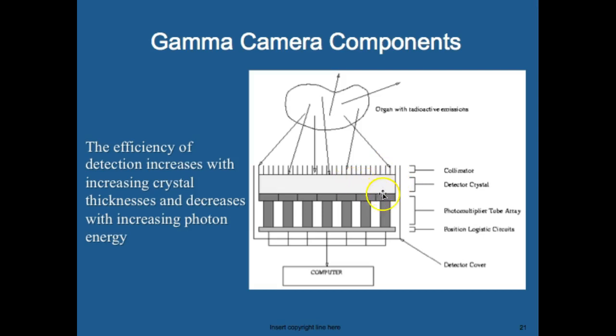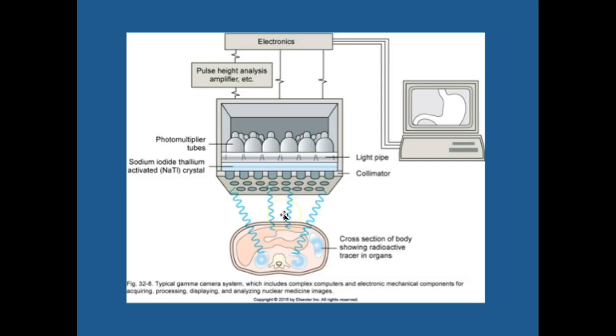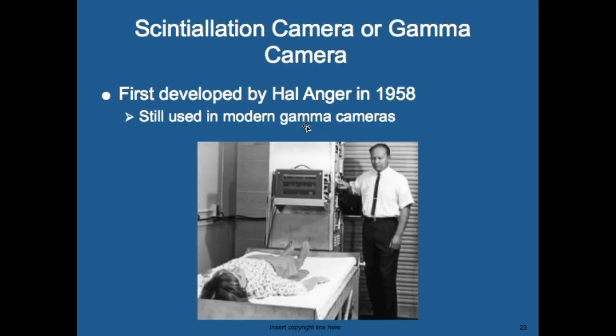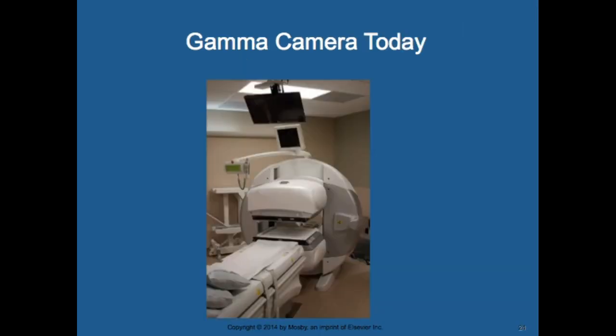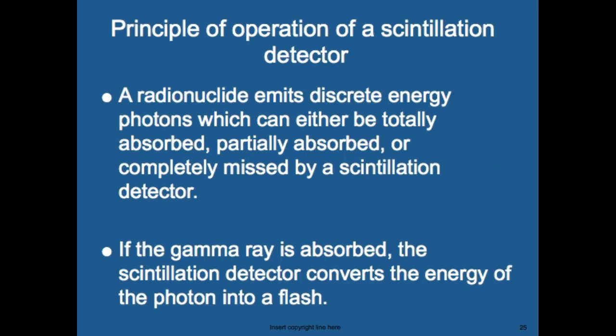Here's the layout: the patient is followed by the collimator, then the sodium iodide crystals, then the light pipe, then photomultiplier tubes, and finally the electronics. The scintillation camera or gamma camera was first developed by Hal Anger in 1958 and is still used in modern technology.